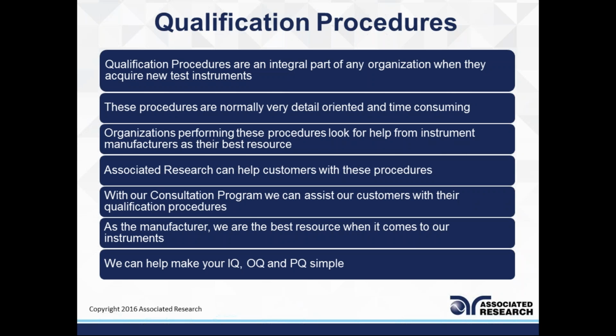And then lastly, we have what's called PQ, which is Performance Qualification. This is the final step in the qualification process for equipment, and it involves verifying and documenting that the equipment is working reproducibly within a specified working range, meaning that you can keep running the instrument and keep reproducing the same results consistently without having any problems. That's what's done in PQ, your performance qualification.